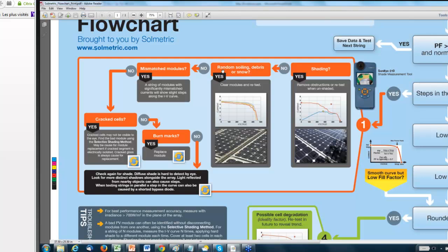If you don't have these issues, then you go further to the left. Well, maybe you have mismatched modules because some of the modules have been replaced over time with modules that don't have the same short circuit current. Well, if they're all original modules and none of those are issues, then you look for other things like cracked cells within one of the modules, or maybe there's a place where there's a burn mark, or maybe you can't even see the burn mark, but maybe there's a hot spot caused by a high resistance effect that's causing a bypass diode to partially turn on. So that's the way you use this chart.